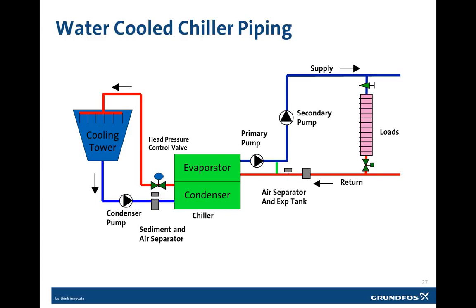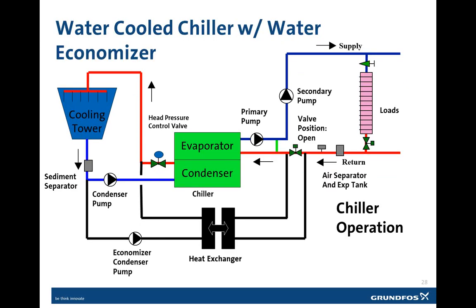And then two additional piping loops exist inside the building to distribute the chilled water to the space loads such as the coils. One of these loops is the primary loop, and the other is the secondary loop. The details of this piping configuration are important so that we can see the difference compared to the piping systems that incorporate the water economizer. So with the water economizer, an additional piping loop is added to the system, shown here in black. If we ignore this new loop, the piping matches the previous slide.